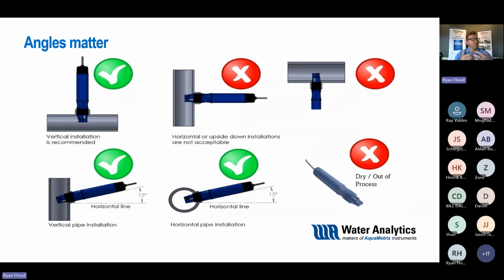Other ways to really highlight how you can be an expert: angles matter. The way you install it on site is really important too, given how the pH sensor works. You want it in a vertical installation, or a slight angle off the horizontal line, to get good readings throughout the life of the sensor — versus putting it completely horizontal or upside down, which could cause issues with your readings, or simply not having it in the process at all.